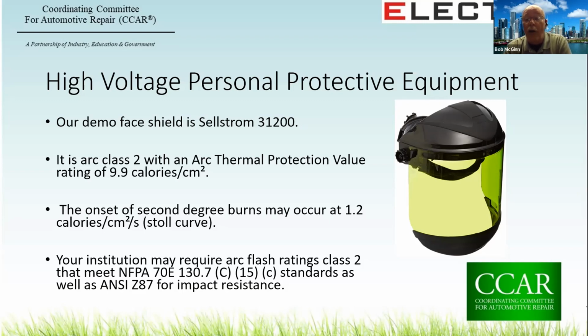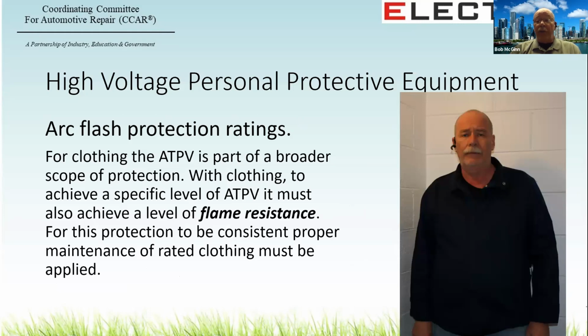Your institution may require an Arc Flash 2 rating that meets NFPA 70E, 130.7, yada, yada. Check with your safety professionals, unless that's you. That would be the minimum that I would recommend for your students. And when we're discussing rated clothing, like the jacket pictured here, it is important to realize that for clothing to be ATPV rated, it will inherently acquire a level of fire resistance, or better termed flame resistance. To maintain this proper flame rating, it will have to be maintained in a certain method.